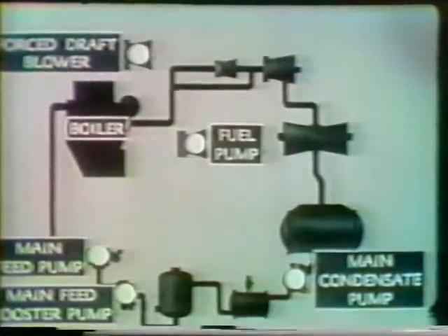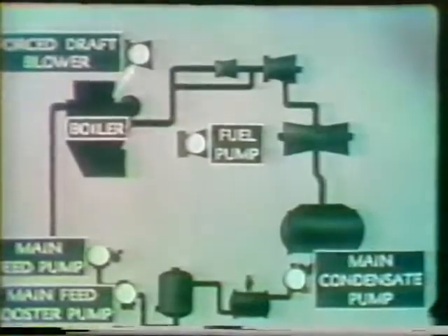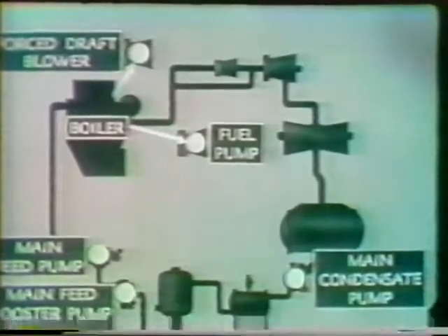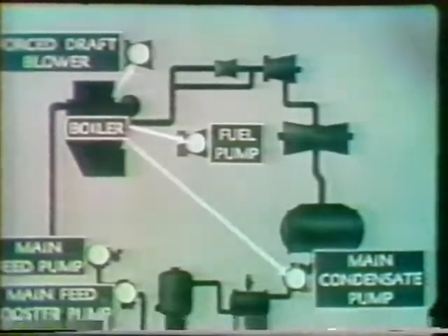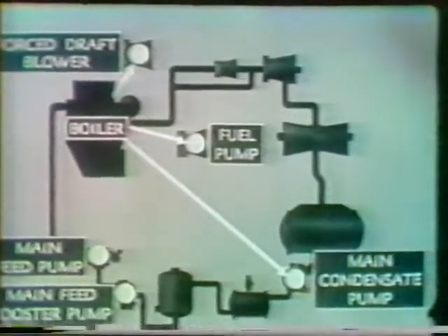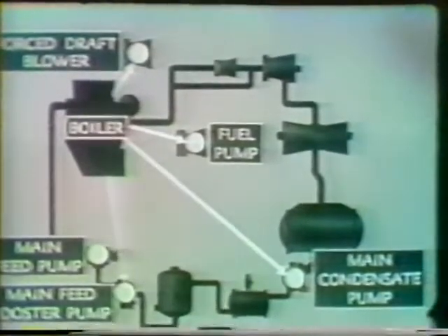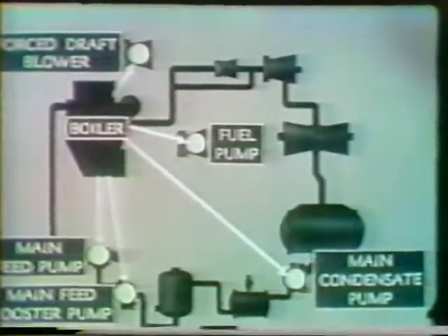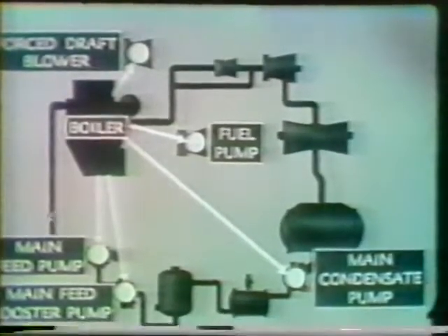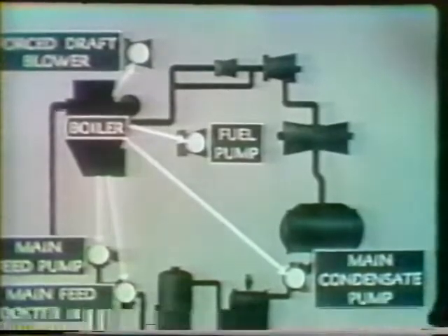The boiler also supplies steam for the auxiliary turbines and generates steam for the turbines which drive the boiler's air blowers and fuel supply pumps, supplies steam for the main condensate pump turbine, and steam for the turbines which operate the main feed booster pump and the main feed pump and other auxiliary turbines. The exhaust steam from these turbines goes to the deaerating feed tank. Here, as we have seen, it is used to remove air and to heat the feed water.